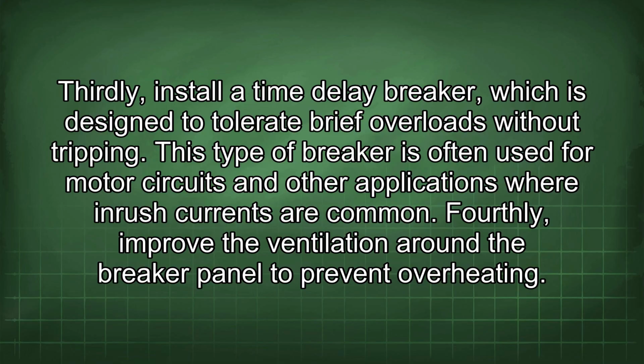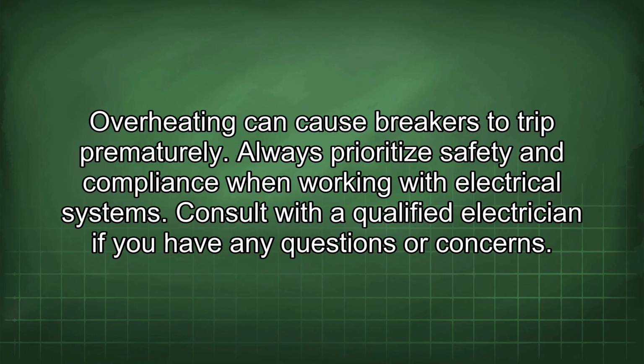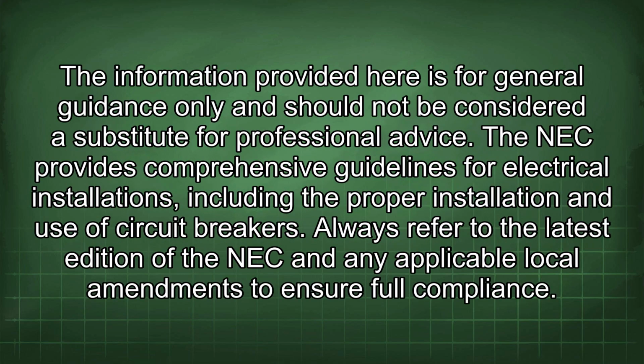Fourthly, improve the ventilation around the breaker panel to prevent overheating. Overheating can cause breakers to trip prematurely. Always prioritize safety and compliance when working with electrical systems. Consult with a qualified electrician if you have any questions or concerns. The information provided here is for general guidance only and should not be considered a substitute for professional advice. The NEC provides comprehensive guidelines for electrical installations, including the proper installation and use of circuit breakers. Always refer to the latest edition of the NEC and any applicable local amendments to ensure full compliance.